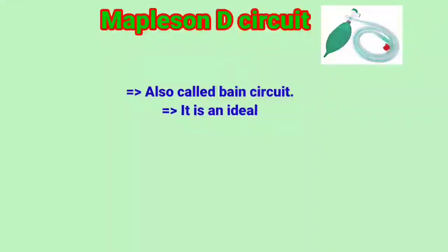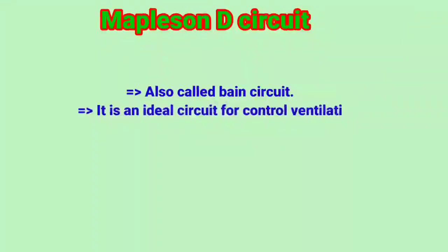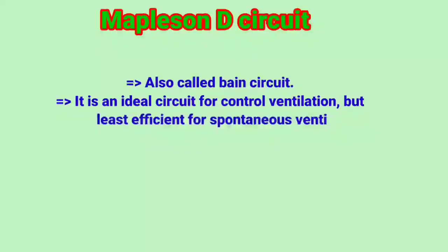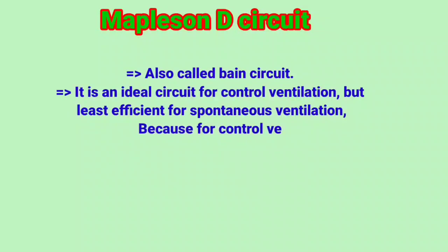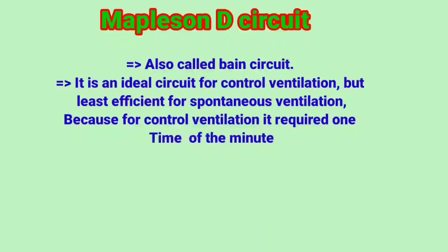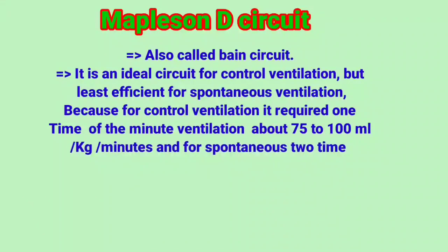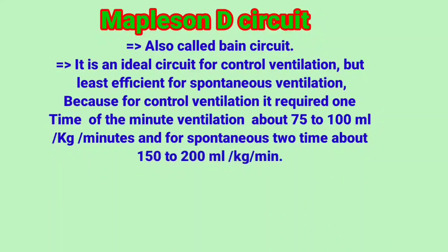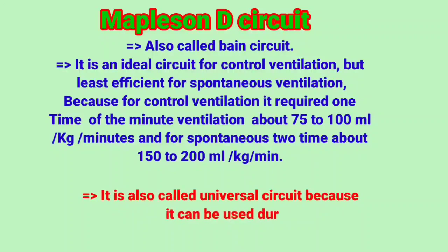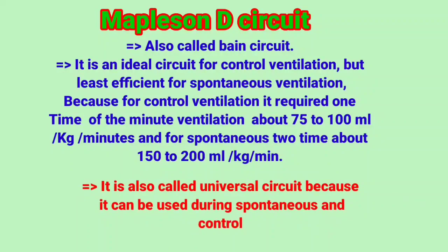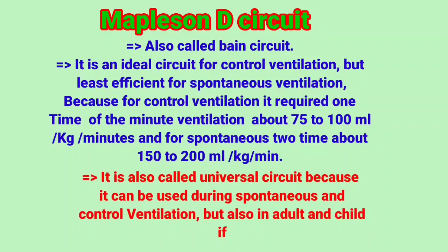Mapleson D circuit, also called the Bain circuit. It is an ideal circuit for controlled ventilation but least efficient for spontaneous ventilation. For controlled ventilation it requires approximately one times the minute ventilation, about 75 to 100 ml per kg per minute, and for spontaneous ventilation two times, about 150 to 200 ml per kg per minute. It is also called the universal circuit because it can be used during both spontaneous and controlled ventilation, and in both adults and children if no other option is available.